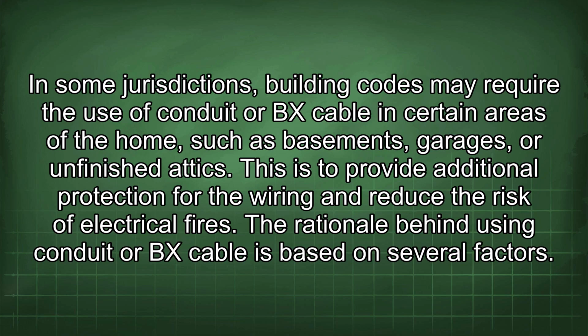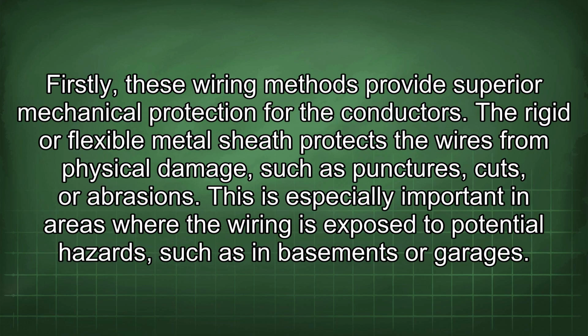The rationale behind using conduit or BX cable is based on several factors. Firstly, these wiring methods provide superior mechanical protection for the conductors. The rigid or flexible metal sheath protects the wires from physical damage, such as punctures, cuts, or abrasions. This is especially important in areas where the wiring is exposed to potential hazards, such as in basements or garages.